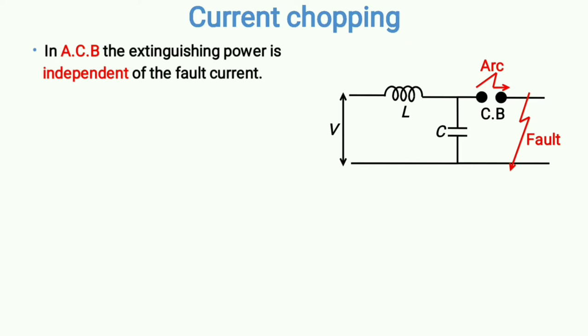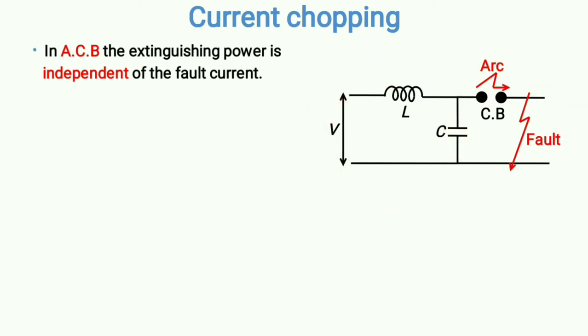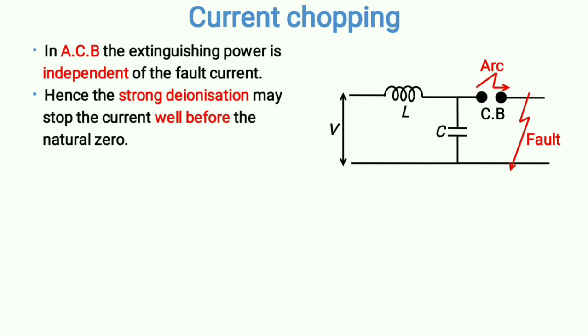This circuit diagram is the same one discussed in the previous video lecture. Although the arc and capacitance don't coexist simultaneously, I have drawn them together for general illustration — when arc is present, capacitance is not, and vice versa. The key point is that the strong deionization may stop the current well before the natural zero.